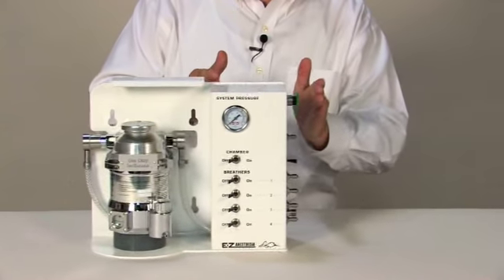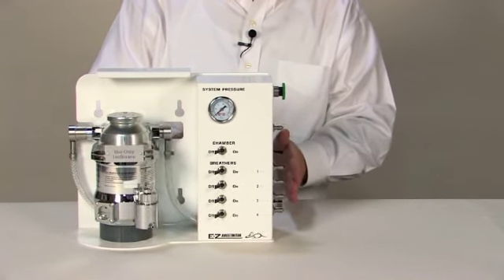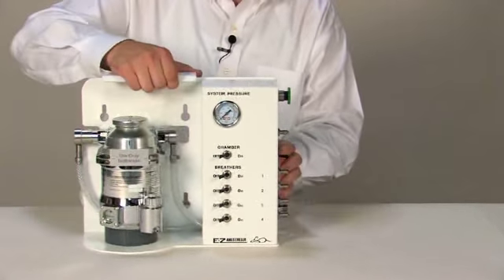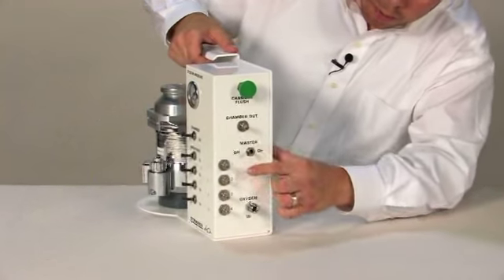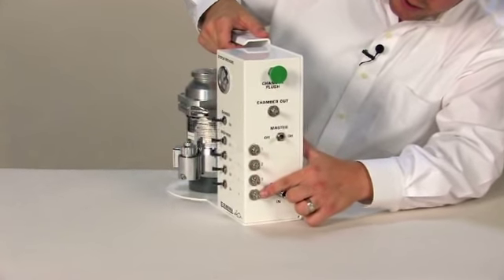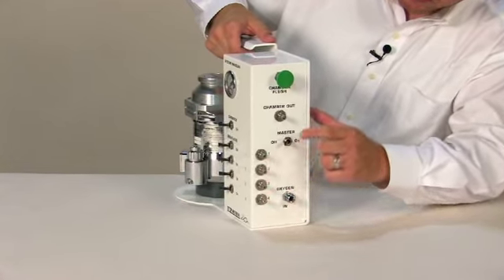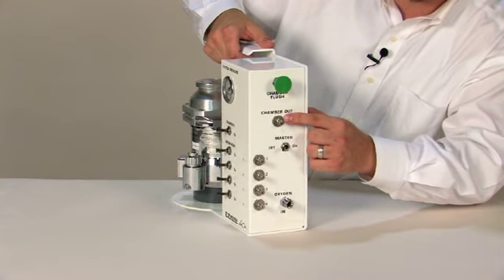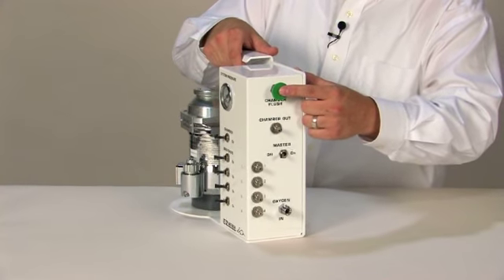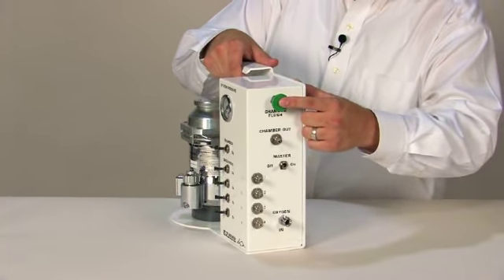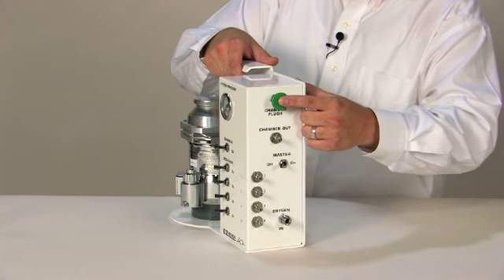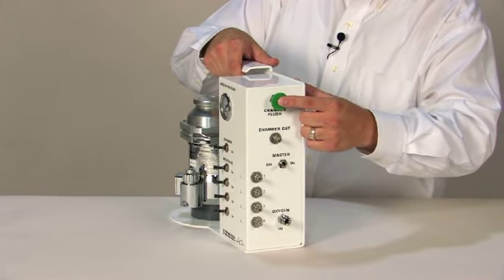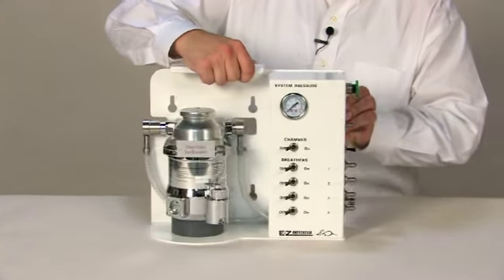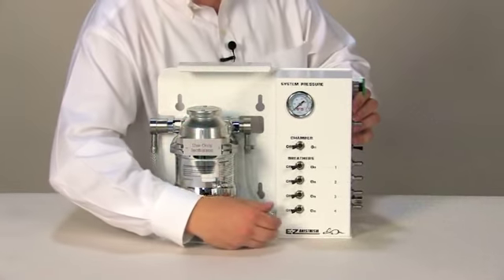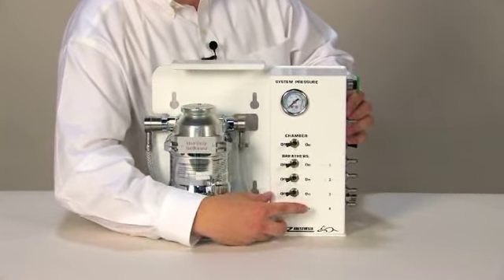This side delivers the anesthetic vapor to the various components of the system. Up to 4 breathers can be connected to any of these 4 outputs. The induction chamber is connected to this output. This green button is a pure oxygen flush for the induction chamber. This will clear anesthetic from the induction chamber prior to transferring animals to the breather. Each circuit is individually controlled using simple on-off switches.